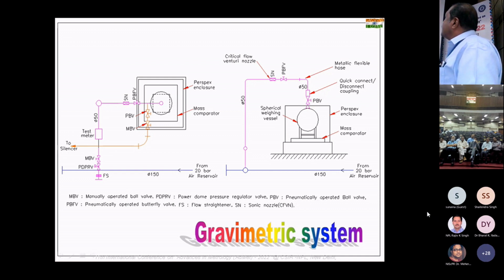We introduced a critical flow venturi nozzle in between. As some of you might know, as long as a nozzle is in critical or choked condition, the downstream pressure rise will not pass to the upstream side. The critical ratio will be somewhere around 0.8, that is, if the pressure ratio of downstream to upstream is about 0.8 or less, we can say it is in a critical condition. And in that case, this pressure rise will not pass to the upstream side. So when we keep a nozzle inside and allow the flow into the chamber, the pressure rise will not pass to the other side.